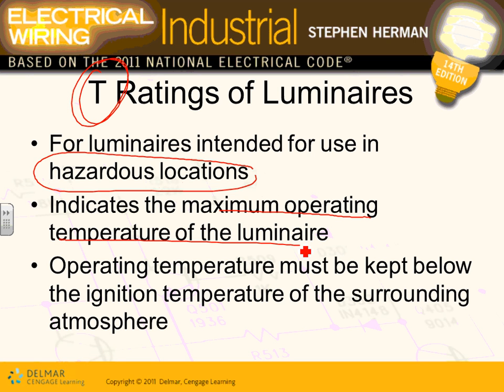When you see a T on the fixture, it will tell you the maximum operating temperature of this fixture is 500 degrees Fahrenheit. So the operating temperature of that fixture must always be kept below the igniting temperature of the surrounding atmosphere. So when they make fixtures for classified locations, they give them a T rating. If it says T1, then it can't be used above this temperature. Otherwise, it will ignite. So you're going to see the temperature rating of them.